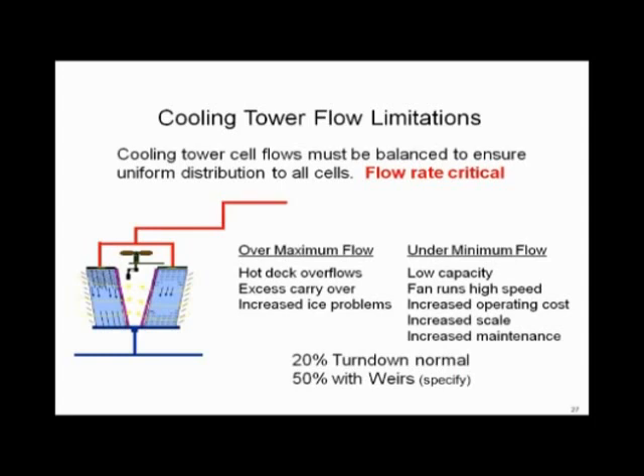This can easily be handled in your guide specifications by requiring all towers to have a mandatory 50% turn down using something called a weir dam. Also, ASHRAE 90.1 2010 energy code now dictates that all cooling towers must have 50% turn down to meet code, so this is coming your way regardless.